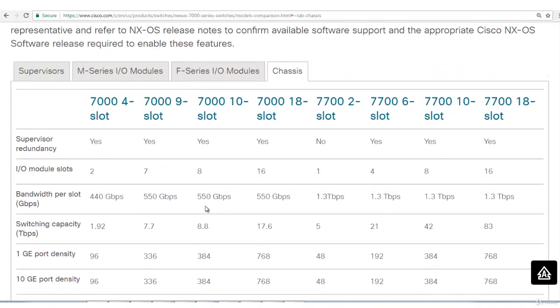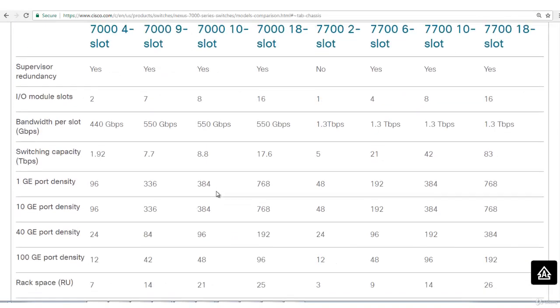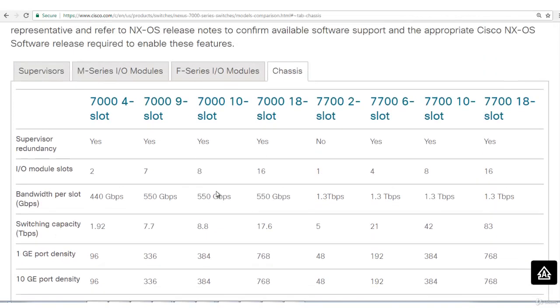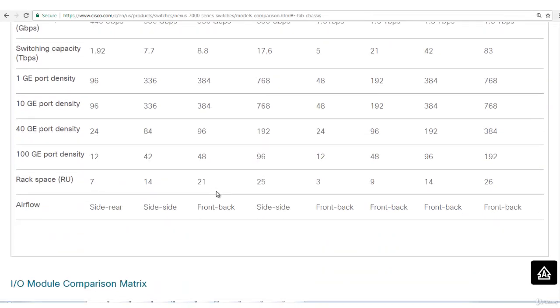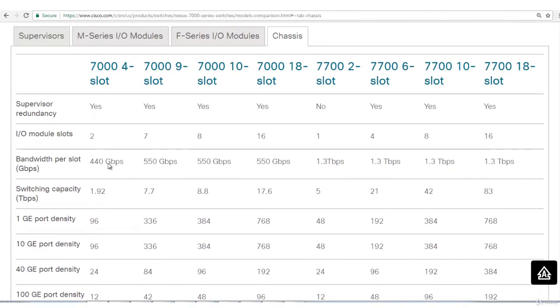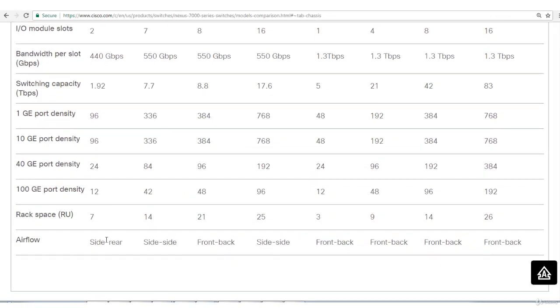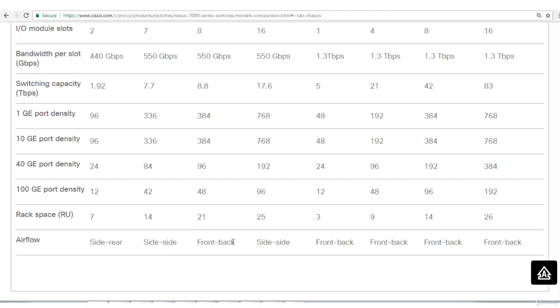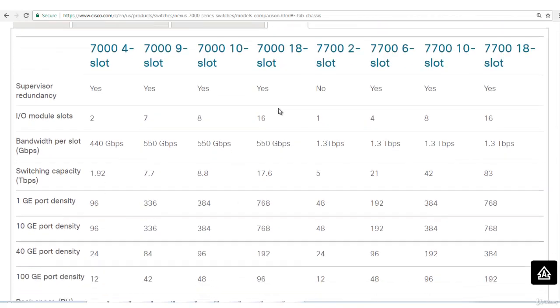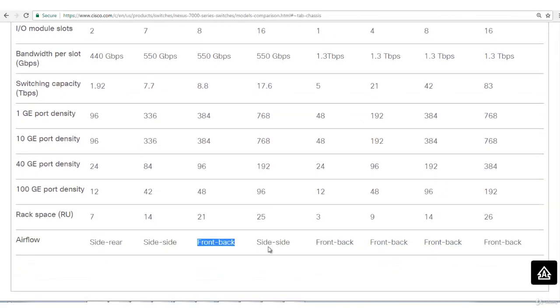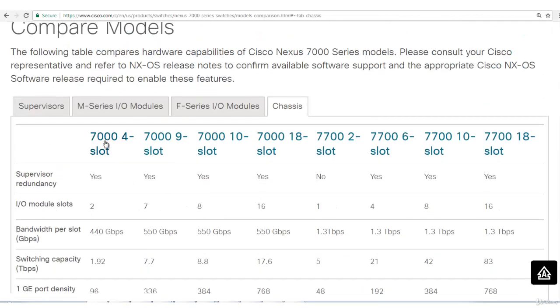The other important thing is airflow. These devices really generate a lot of heat, so you need to have proper airflow. When you have 7004 series, the airflow will be side to rear. The air will enter from side and exit from rear, that is the back end. For 7009 series it will be side to side. For 7010 series, front to back. The air will enter from front and exit from back. 18 series side to side, and 7702 series front to back.